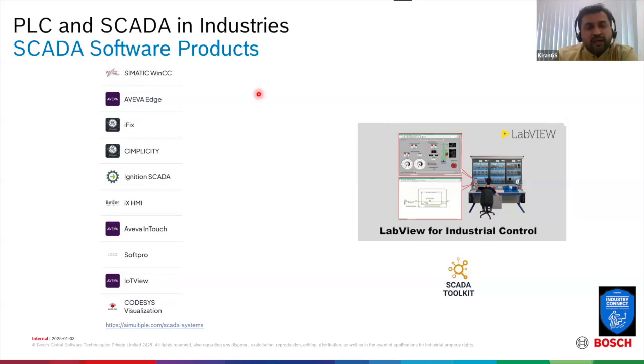Having said that, the PLC manufacturer also has their own SCADA system. For example, Siemens has its PLC called the S7 series, and similarly it has the Simatic WinCC SCADA software. From a SCADA point of view, you can develop a user interface screen using Simatic WinCC and connect all the input output for this UI. From a backend point of view, you can still use the PLC programming language or connect to the PLC itself, where Simatic WinCC will connect to the S7 PLC, and hand in hand it works as a complete solution.